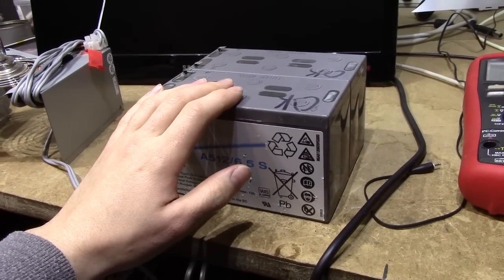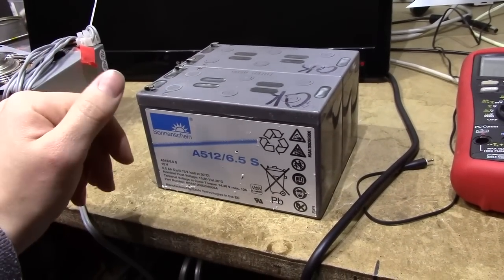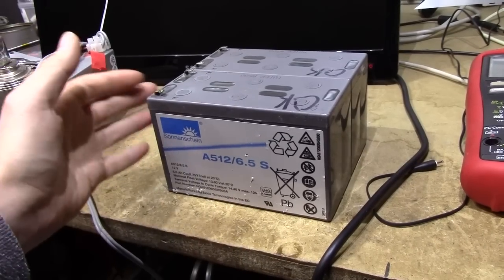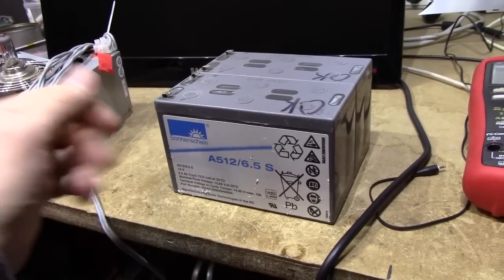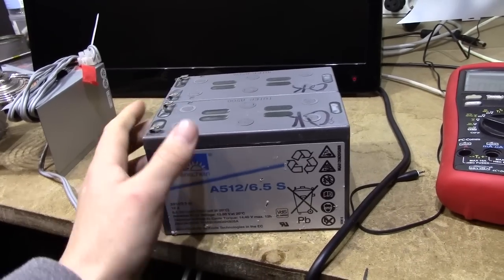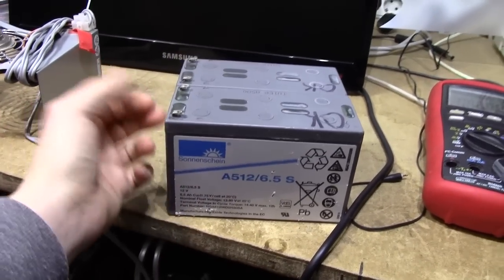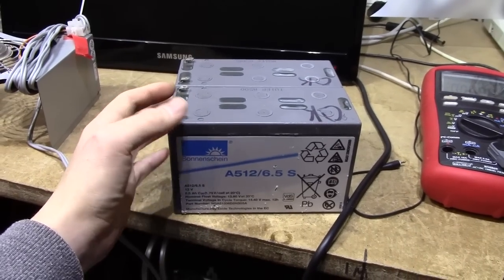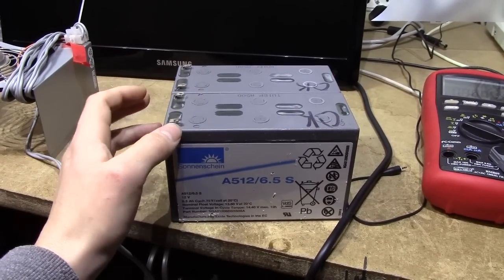All of them had zero volts or below zero. Some actually had a slight negative voltage from having been improperly stored, and then the UPS had been turned on and attempted to charge the batteries, which didn't work quite well.